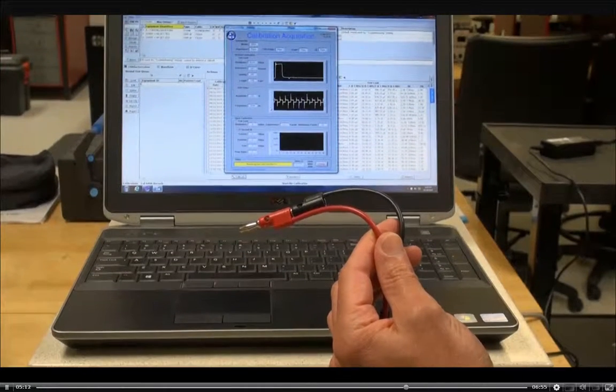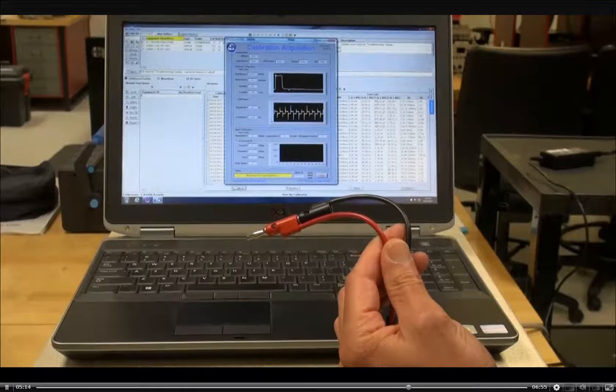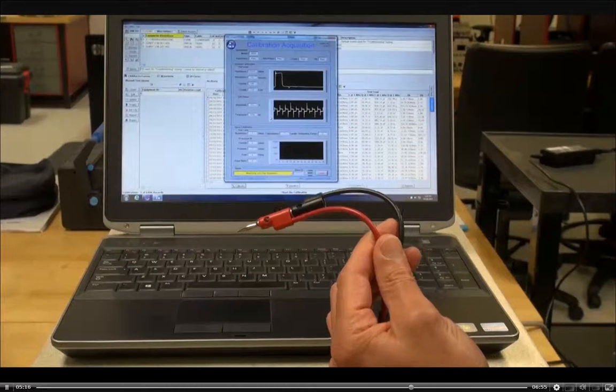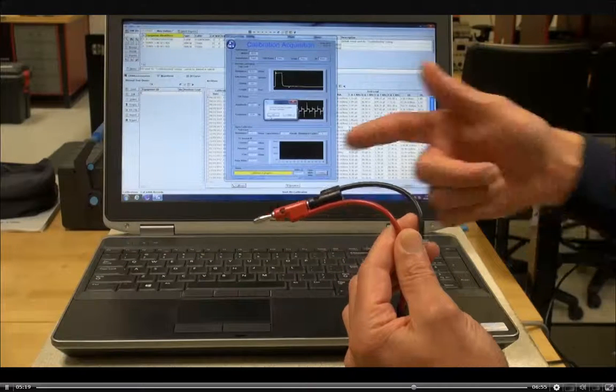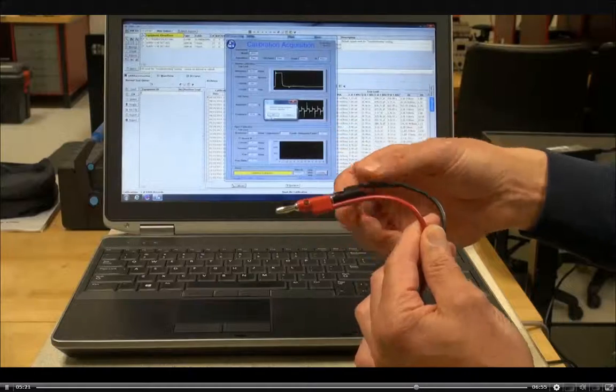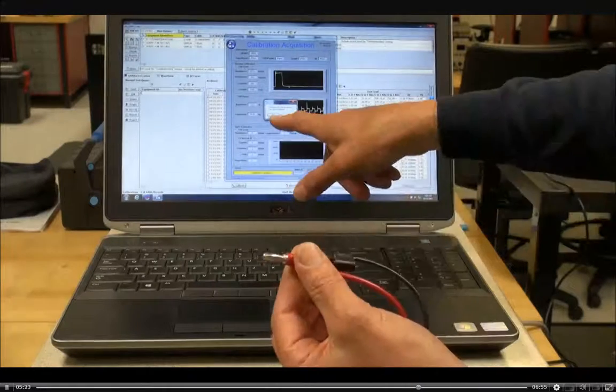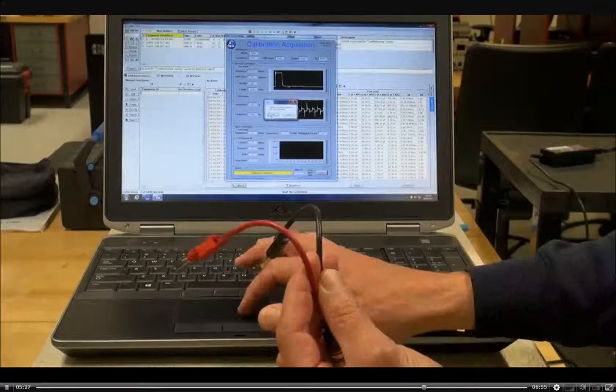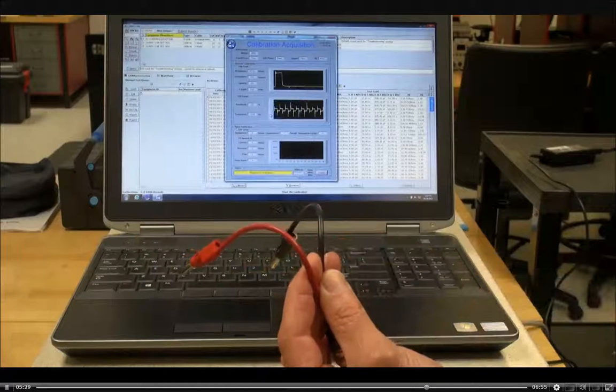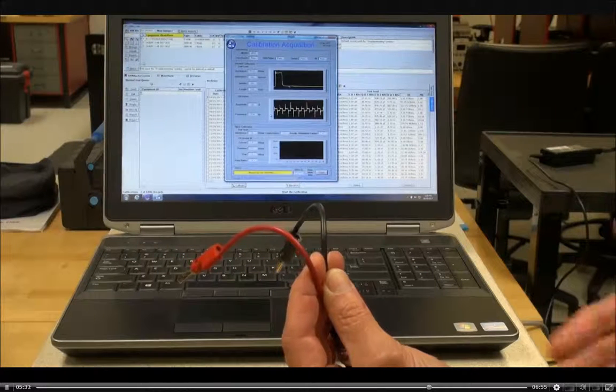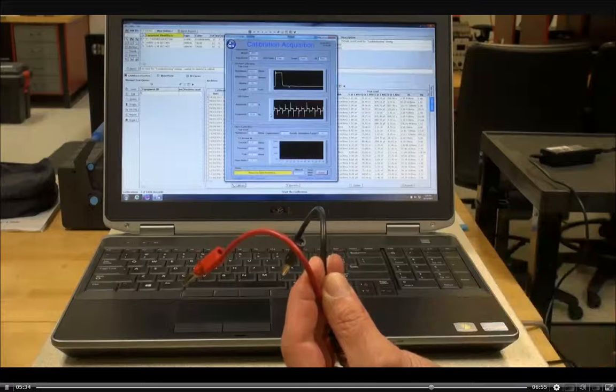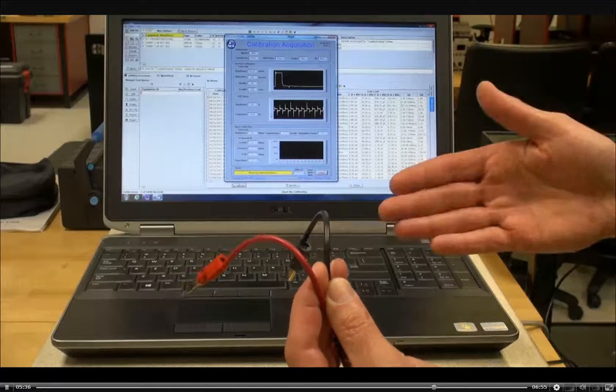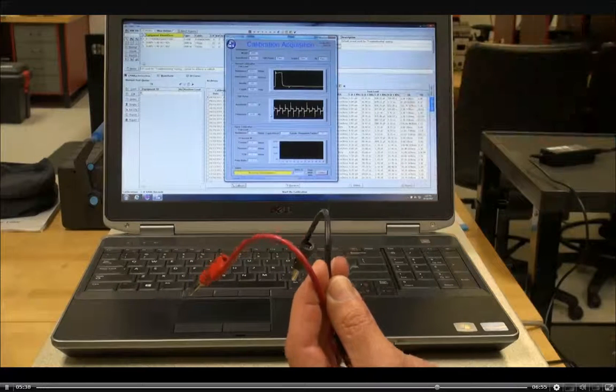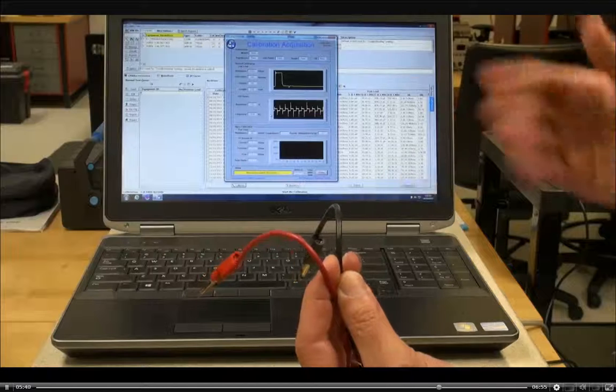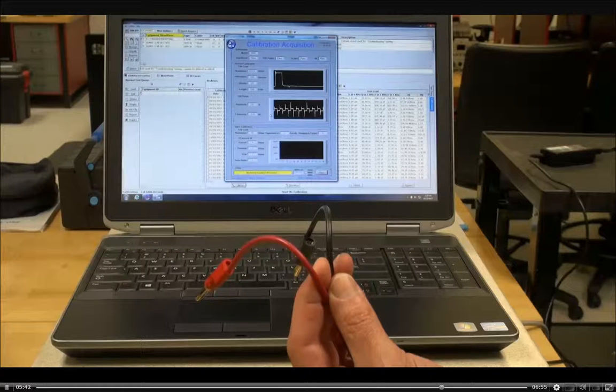Relatively low voltage on these tests, but still a good idea not to touch the end of the cables, mostly just so you don't interfere with the signal. Now it says open the test clips, and again just open them, make sure they're hanging in air so they can't see each other. So like I said, this is nulling out the test cable, this 20 feet of test cable. It did the short test, it knows how long it is, it'll disregard that. So now when you do your testing, the 0 mark will start right where the test clips are.